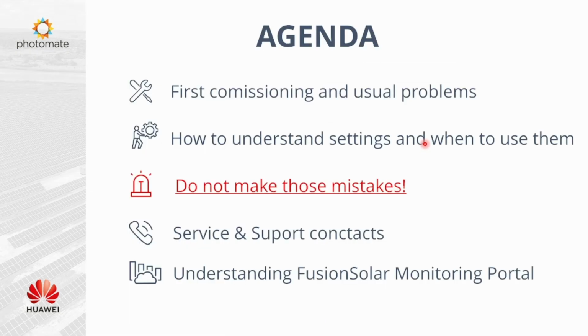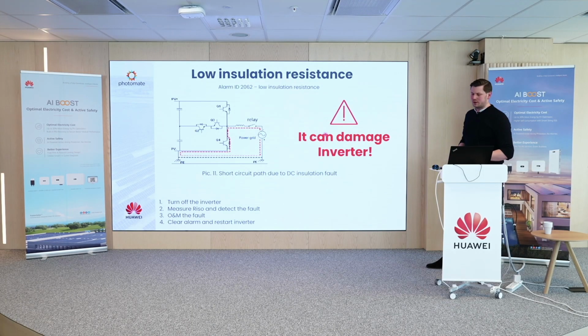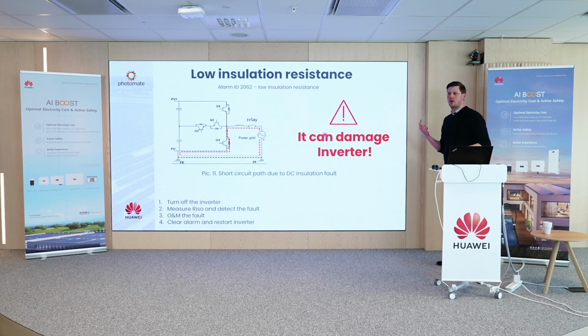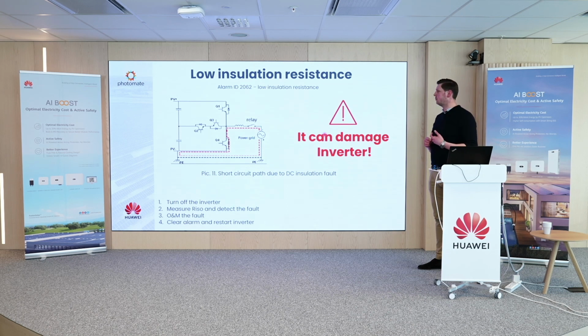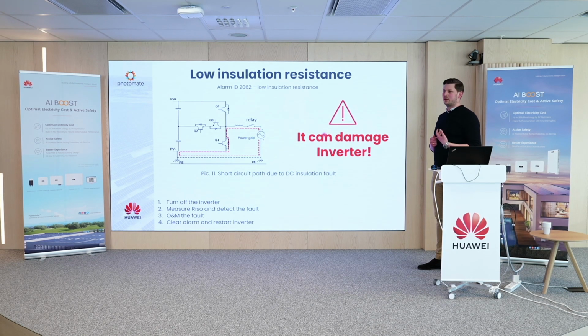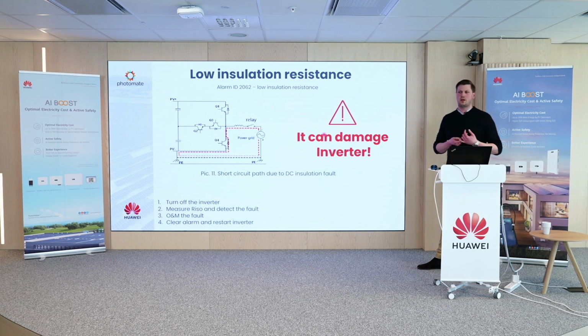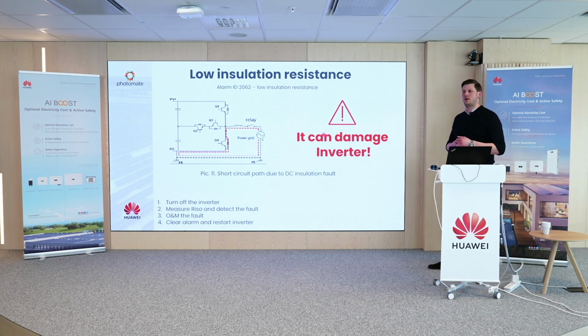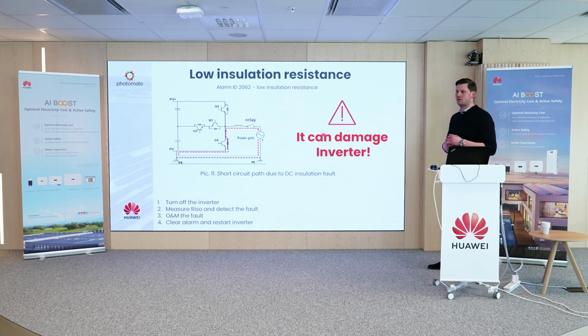Based on our service experience, I have prepared some typical mistakes which happened not only last year, but through the previous years. I just wanted to warn you not to make them, because it might harm you or your equipment. Starting from the beginning, low insulation resistance. This is what you have to be very careful about. The inverter is measuring the insulation resistance on the DC side every time it starts. It's regulated by the standard.